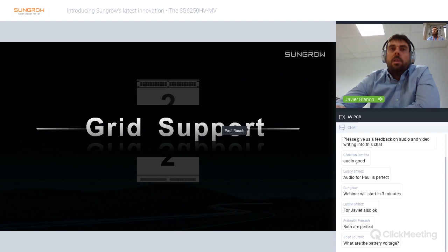Talking about grid support, the second driver of the design of this new solution, we have on the one hand the fast power response together with Q at night function. The reactive power response is unique in this inverter and is verified by third party. We have a response time of reactive power less than 30 milliseconds and active power less than 140 milliseconds. These requirements are really important in the new grid codes, not only in Europe but in many countries all around the globe.